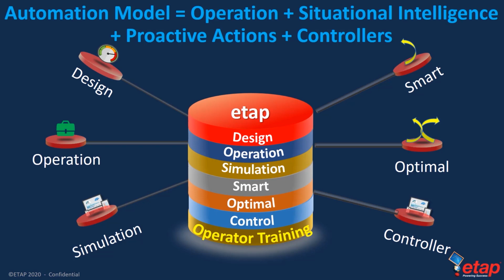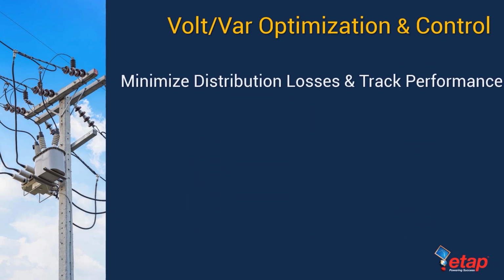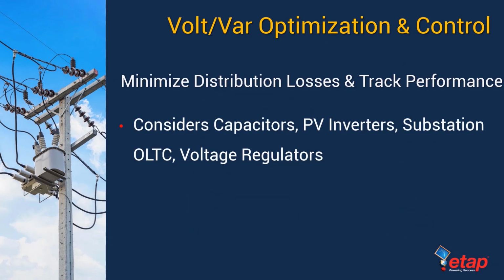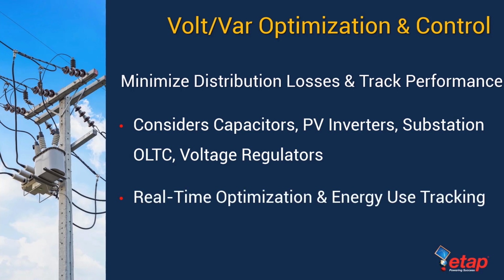And optimization capabilities such as volt-var optimization and control to minimize distribution losses and track performance. This solution takes into account not only load tap changers on transformers, but also capacitors that are in the field, photovoltaic inverters, and voltage regulators. Providing real-time optimization and energy use tracking.